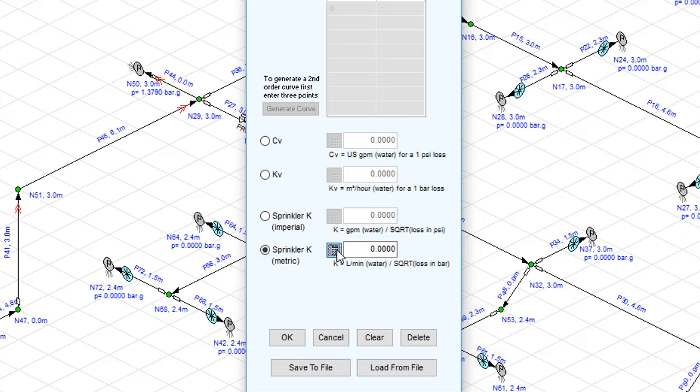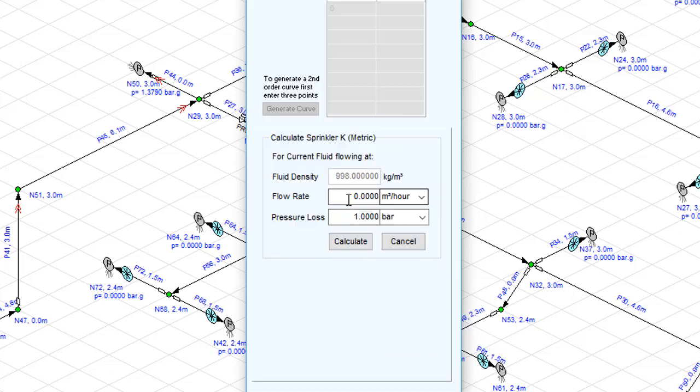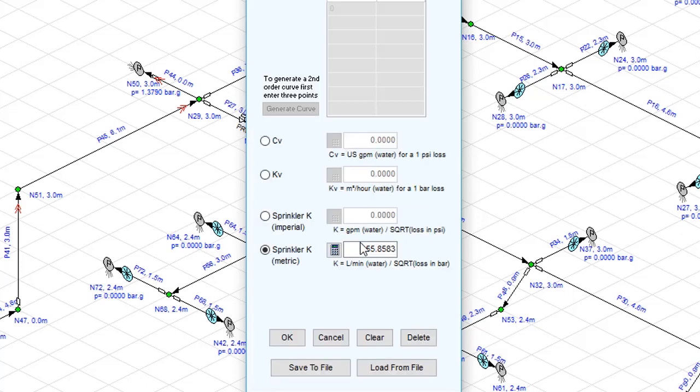Pipe Flow Expert provides you with a helpful calculator tool to compute the sprinkler K factor for a particular flow rate and pressure drop characteristics of a sprinkler based on the current fluid. Using the calculator tool, we find that the sprinkler K is reported to be 55.8583.